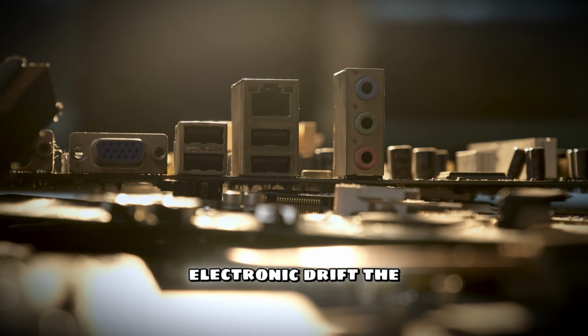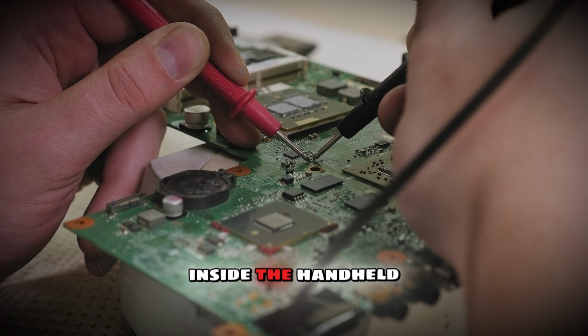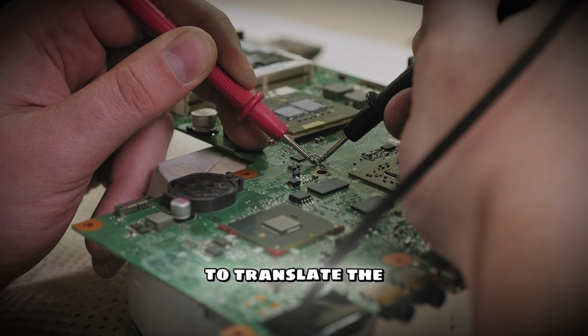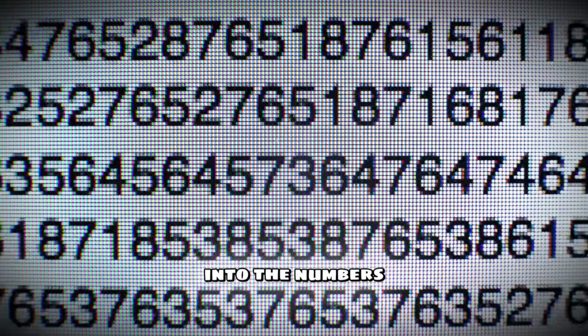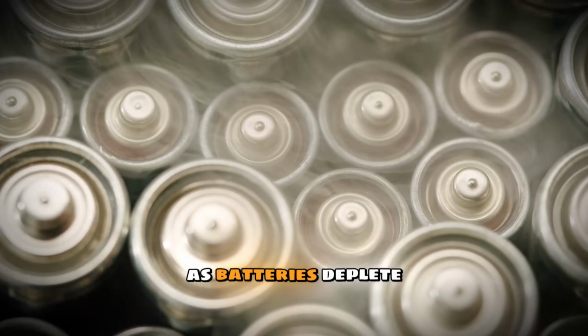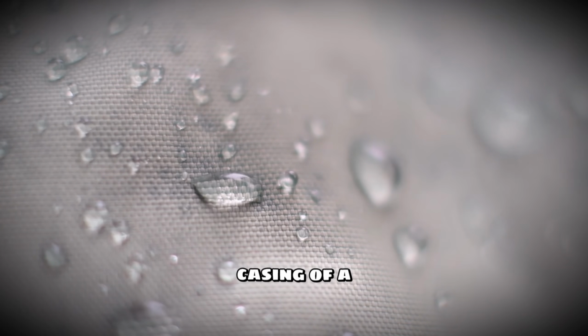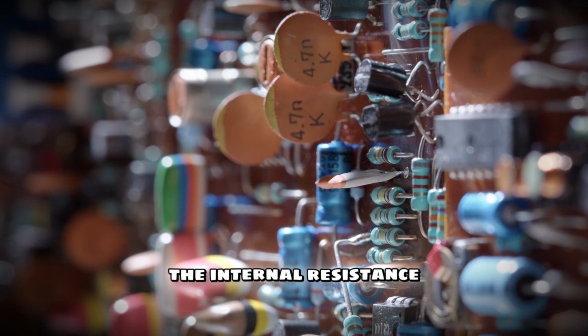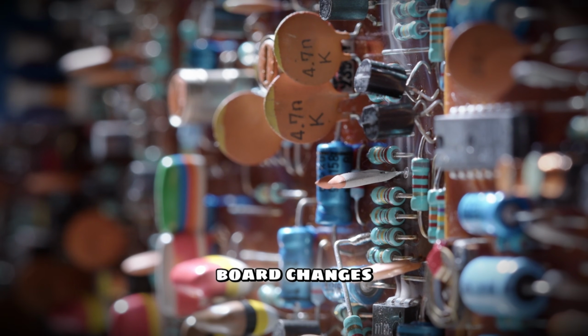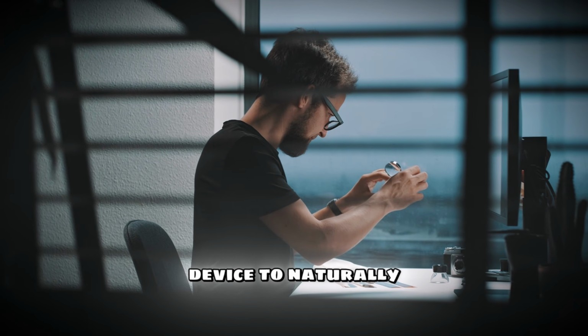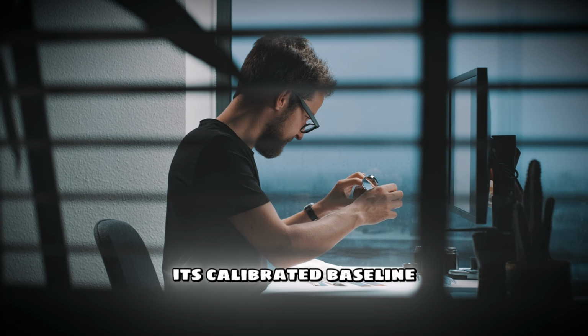Finally, we have electronic drift. The circuit board inside the handheld unit requires a steady voltage to translate the sensor signal into the numbers you see on the screen. As batteries deplete, or if moisture and humidity creep into the casing of a non-waterproof unit, the internal resistance of the circuit board changes. This causes the device to naturally drift away from its calibrated baseline.